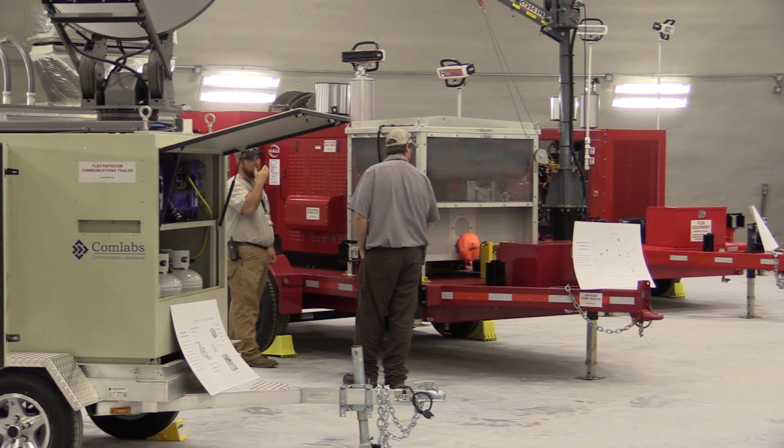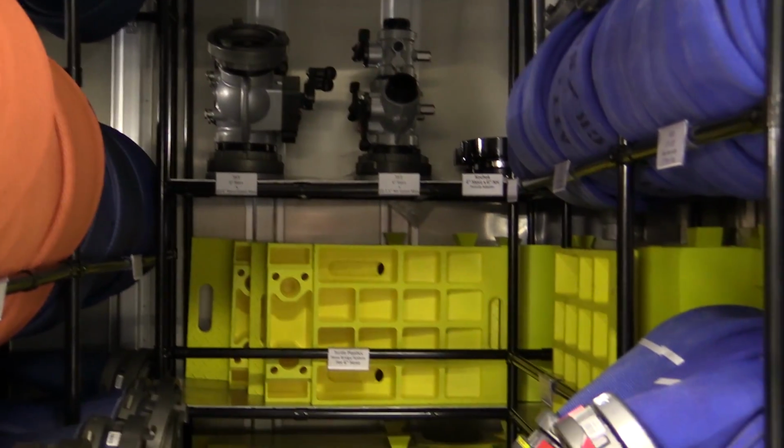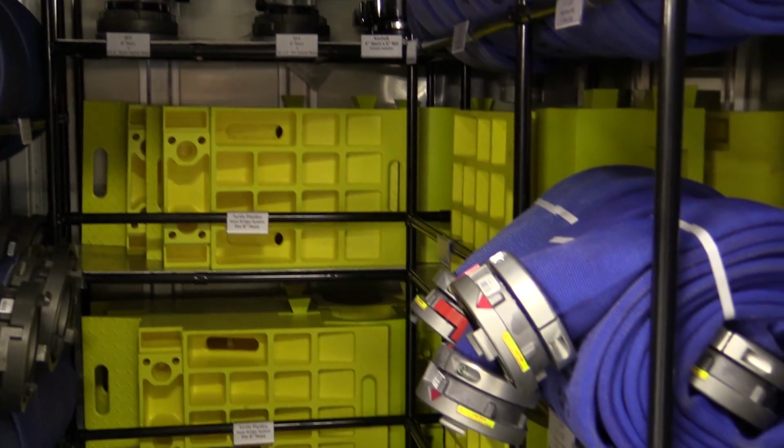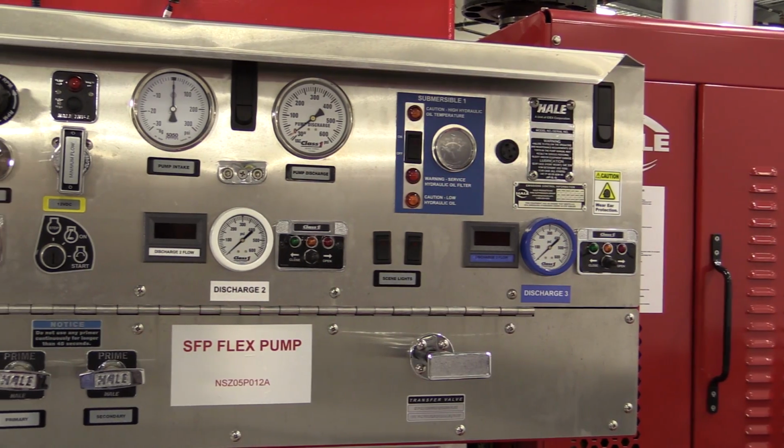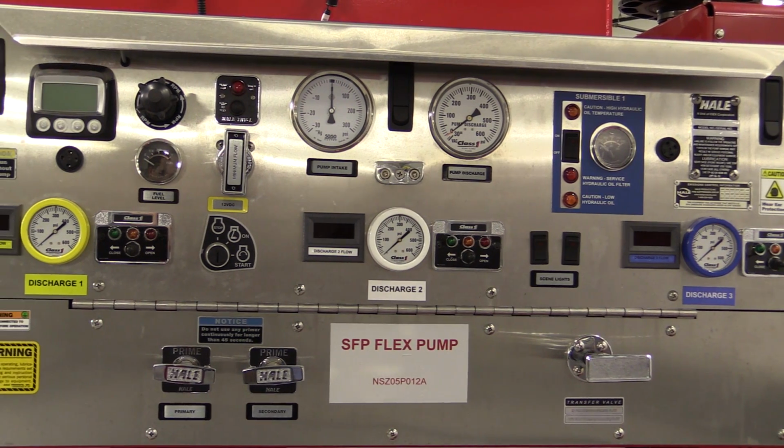There'll be diesel-driven pumps, diesel-driven electric generators, cables, hoses, and miscellaneous types of equipment. This building is going to house 3 sets of equipment. We'll have 1 set for each unit and then a spare set. This new portable equipment, in conjunction with the recently developed strategies and plant modifications, will provide us alternate methods to provide cooling to the nuclear fuel. That's going to add an extra layer of defense to protect the health and safety of the public.